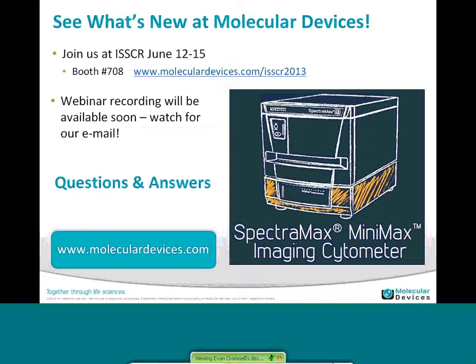There are also questions about timing. One is asking about what magnifications are available and what is the scan time for a 384-well plate. The system uses a 4x objective, which gives sufficient resolution for looking at cell segments. Read time for a 384-well plate is going to be less than 15 minutes — about 12 minutes per 384-well plate, and analysis is done simultaneously.